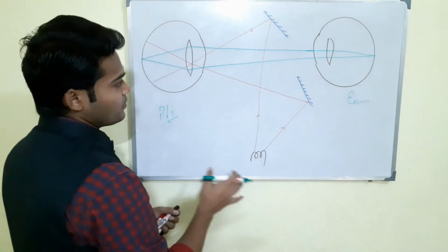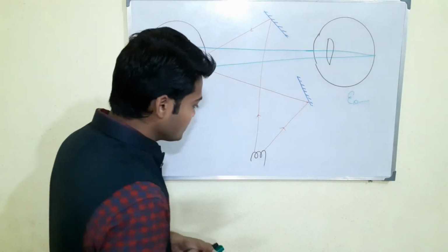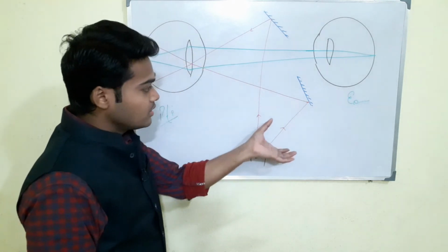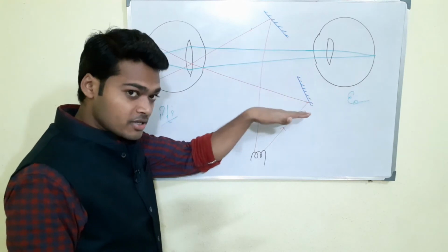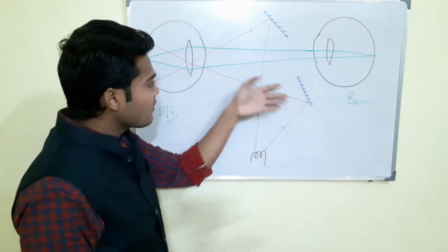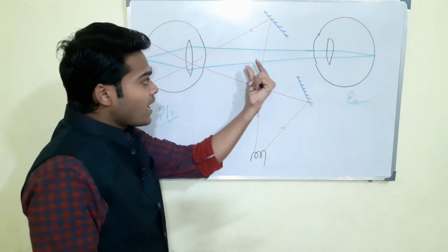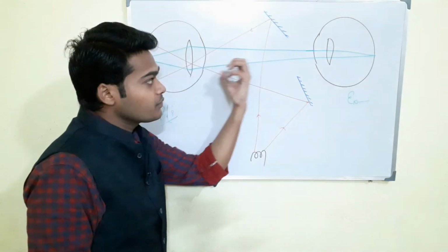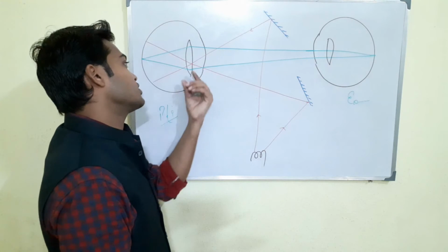So this is the principle for the emmetropic eye. When light glows from here in divergent form, using a mirror, the optical principle of the ophthalmoscope is incorporated in this form. It reflects the light into the patient eye, and after reflecting back from the fundus it reaches the examiner eye, and then evaluation starts.